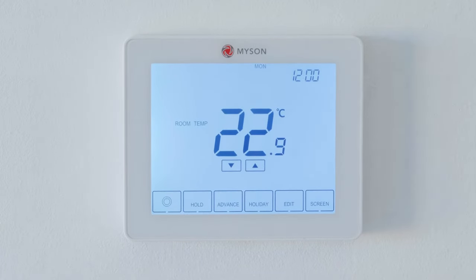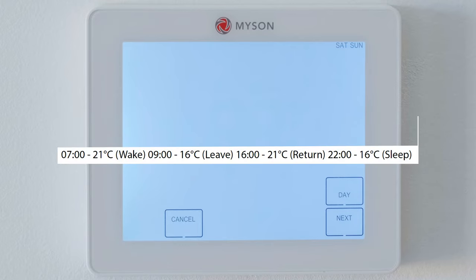The thermostat can be set up with 3 different programming modes. Weekday/weekend, or 5-2, which allows you to program 4 different times and temperatures for the weekday and 4 for the weekend. 7-day program, where you can program 4 times and temperatures independently each day. And 24-hour, where all days are programmed exactly the same and the levels repeat continuously each day. Your unit is defaulted to weekday/weekend and comes pre-programmed with a set of operating times and temperatures that often suit most people.